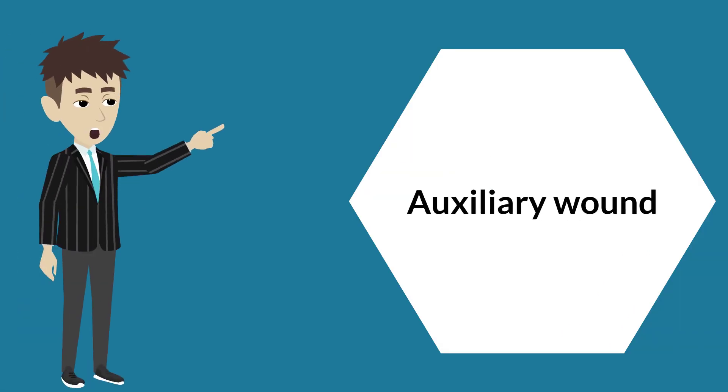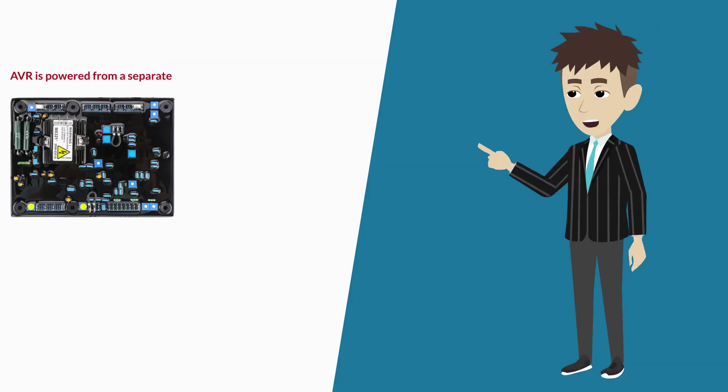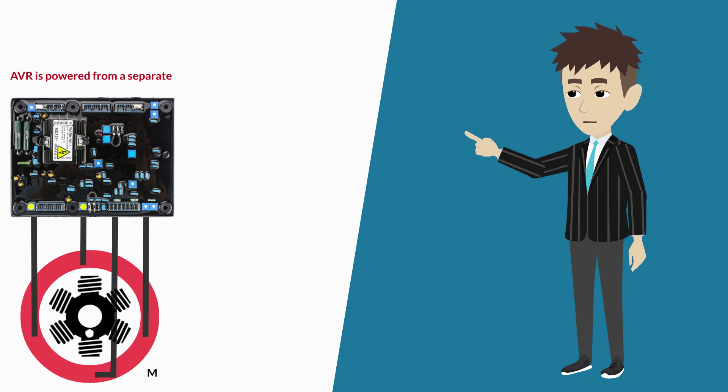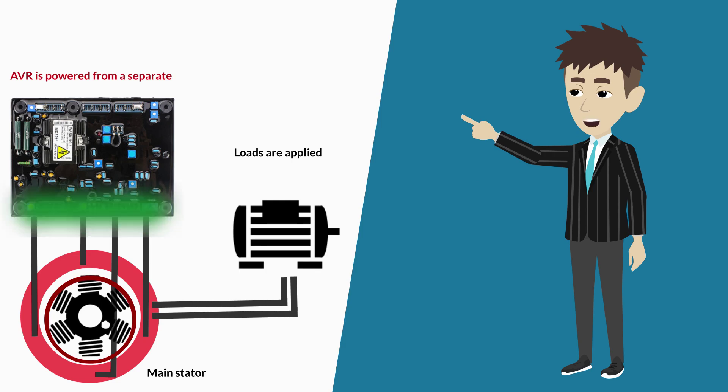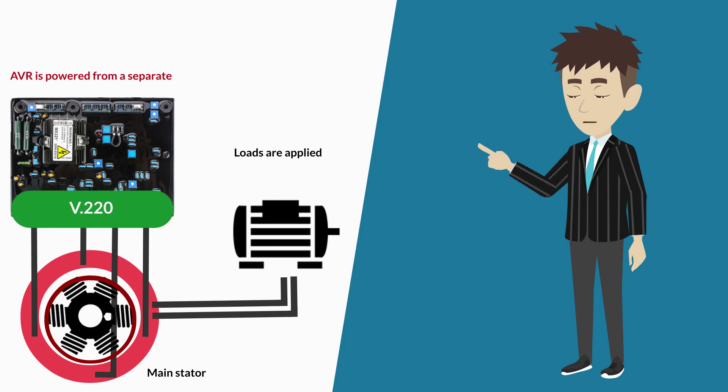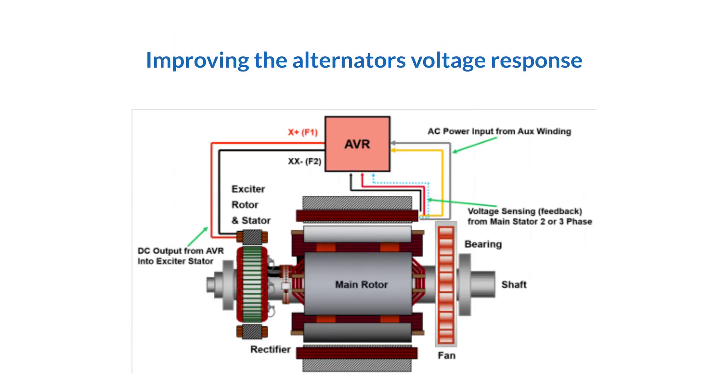With auxiliary wound alternators, the AVR is powered from a separate winding embedded in the main stator. When loads are applied to the main stator, the effect on this separate winding is minimal, improving the alternator's voltage response.